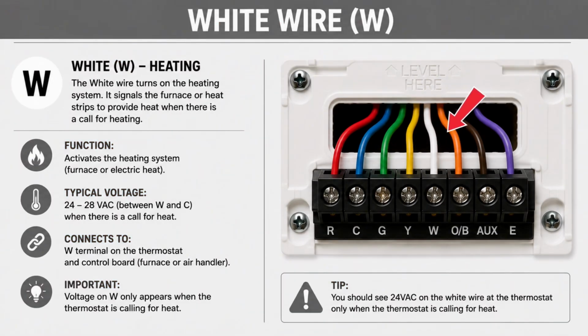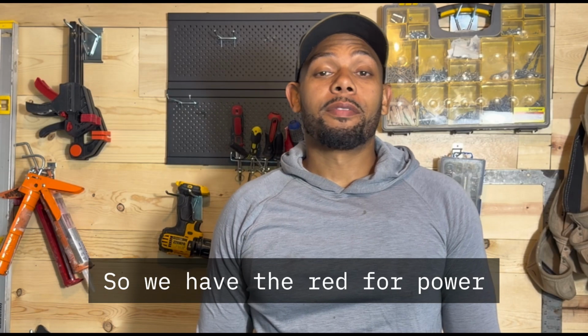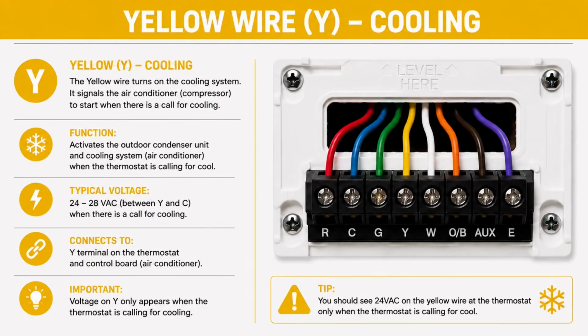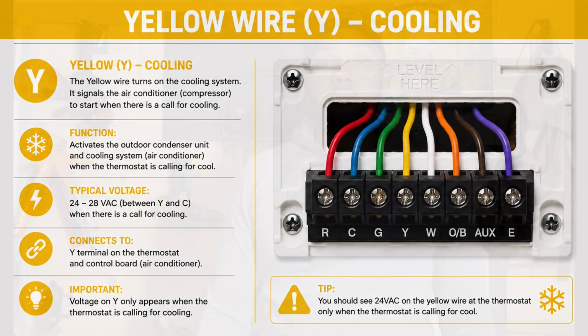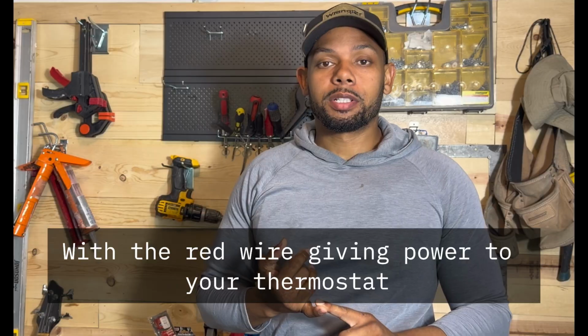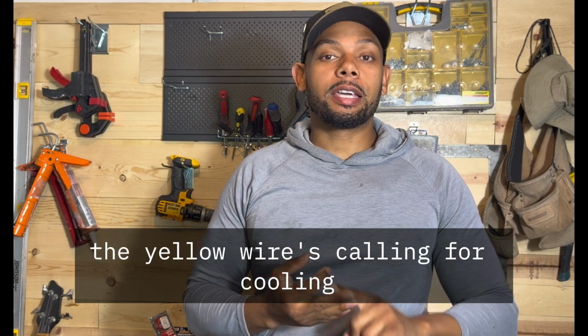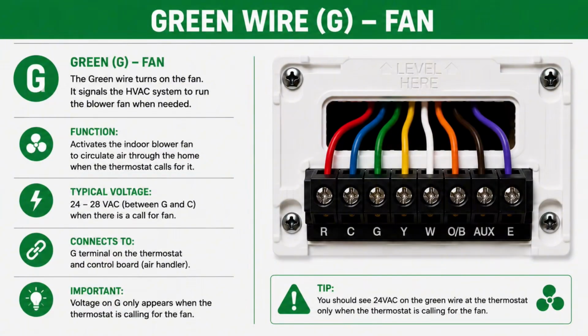Next, we have the white wire. The white wire typically controls the heating system. When the thermostat calls for heat, it sends 24 volts through the white wire to activate the furnace and heat source. So we have the red for power, white for heat. Now we have the yellow that's going to represent the cooling system. This is going to send a call from your thermostat to the outdoor compressor or AC system. With the red wire giving power to your thermostat, the white wire is calling for heating, the yellow wire is calling for cooling, the green wire is going to be for your blower. This blower is located on the inside of your furnace, and this is where all of the forced air goes, coming through your vents and all of your ductwork.